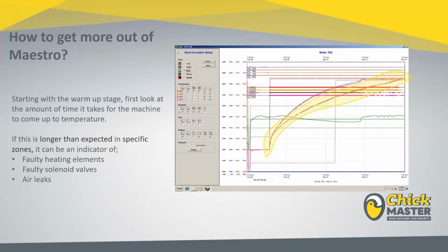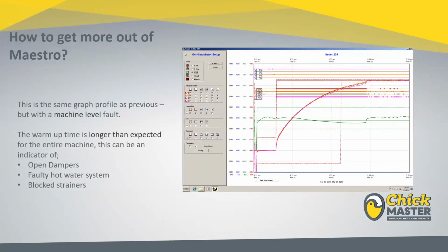And this can be a little bit easier to troubleshoot, but there are several things to look for. When we look at what we call more or less a machine level fault, it's something that causes the whole machine to warm up a little bit later. So this would represent a graph of a machine that had a very extended warm up period. So oftentimes we find a machine like this where all of the dampers are open on the machine. In other words, we're allowing fresh, cool air from the room to migrate into the machine at a heavy rate, causing this extended warm-up period.